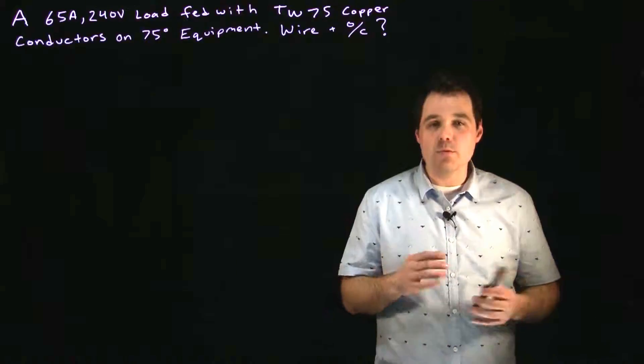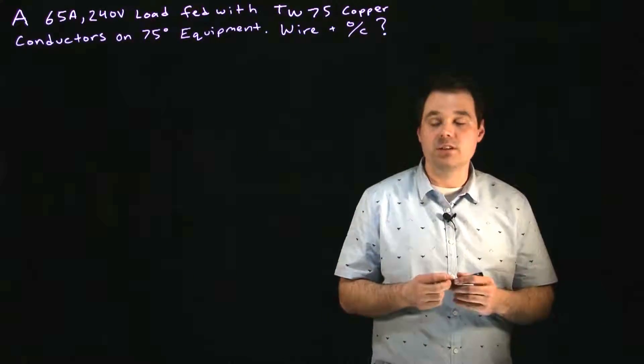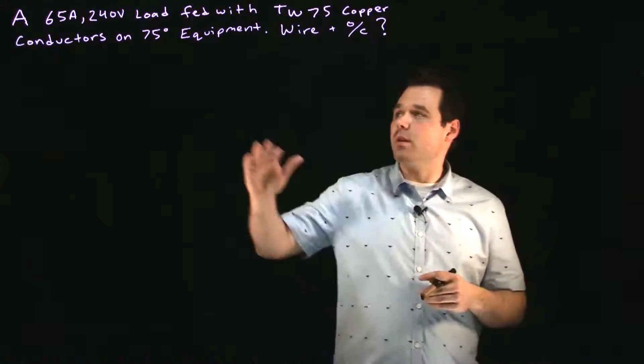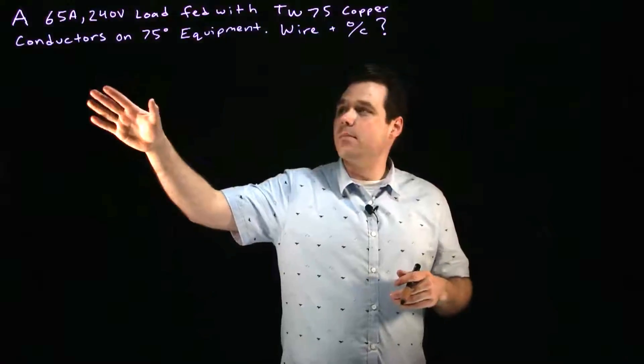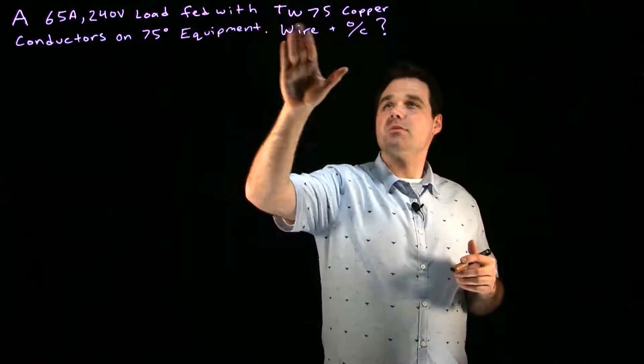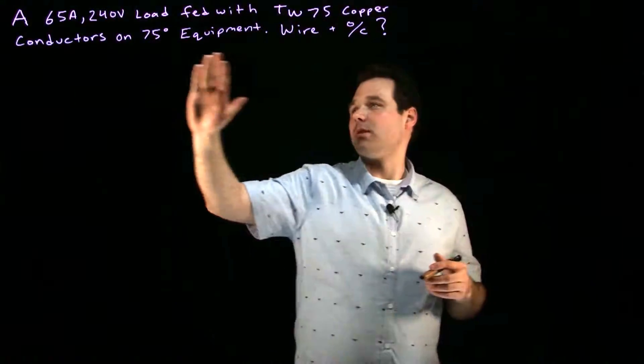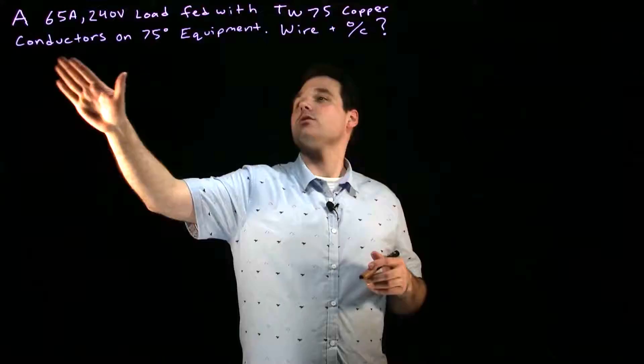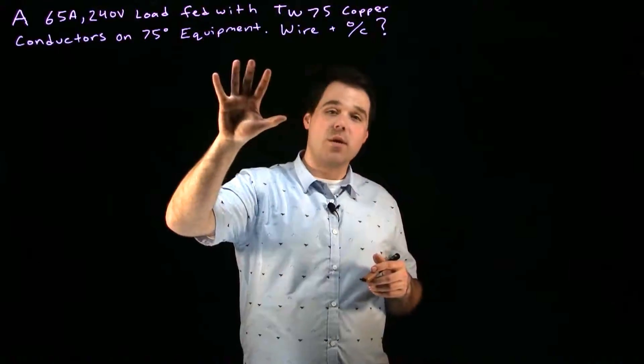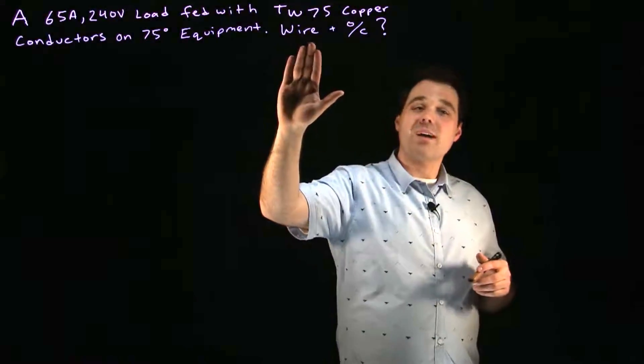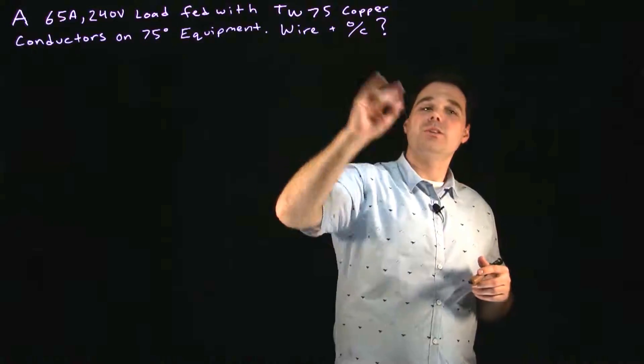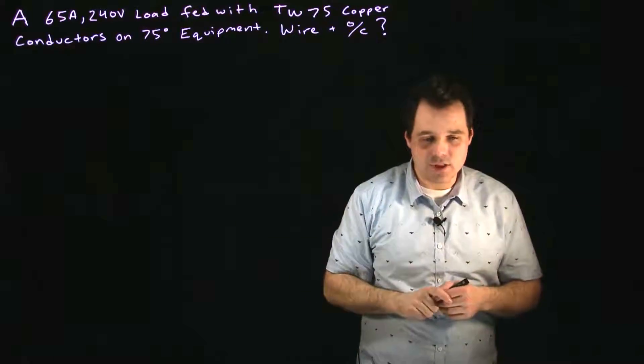There are a couple of important places in the codebook we need to go. The question here is: we have a 65-amp, 240-volt load fed with TW75 copper conductors on 75-degree rated equipment. We want to know what wire size is required for that load and what the overcurrent device size should be.